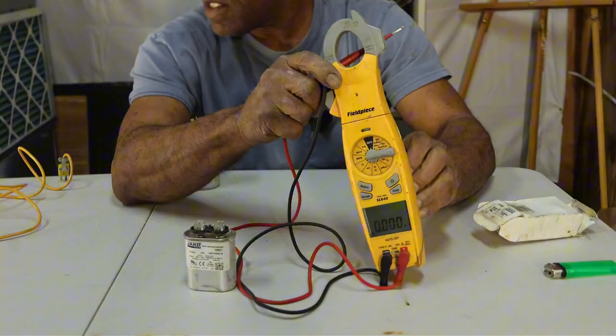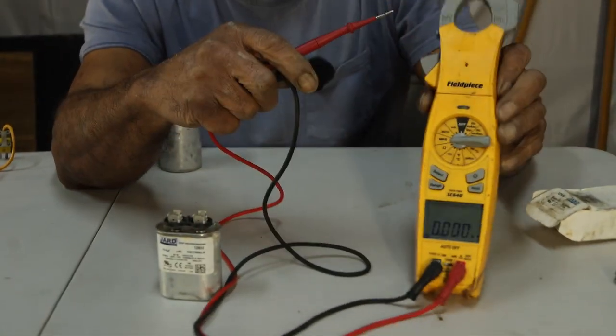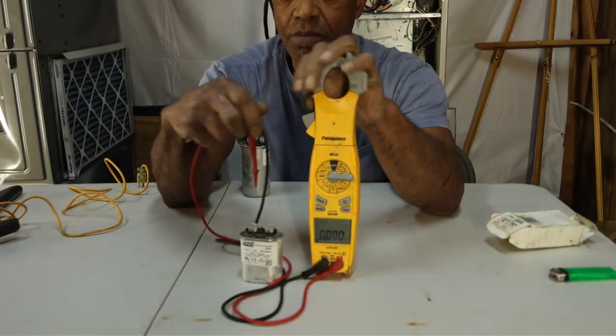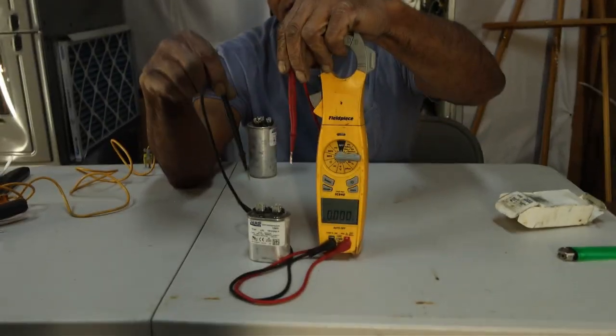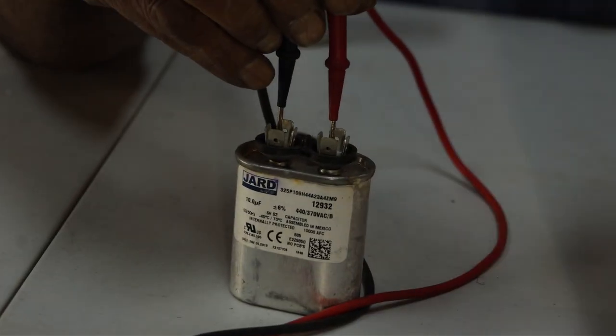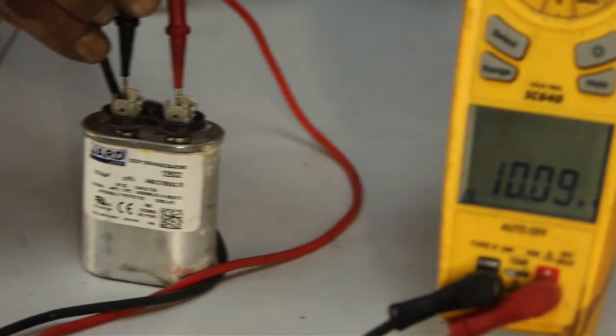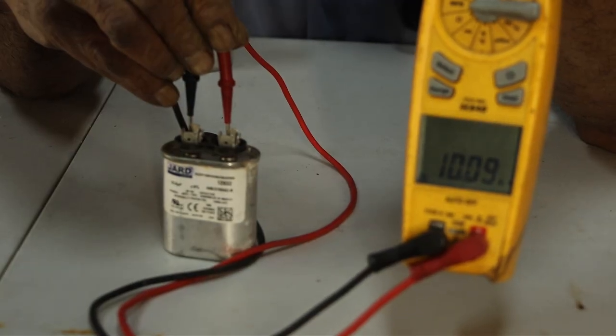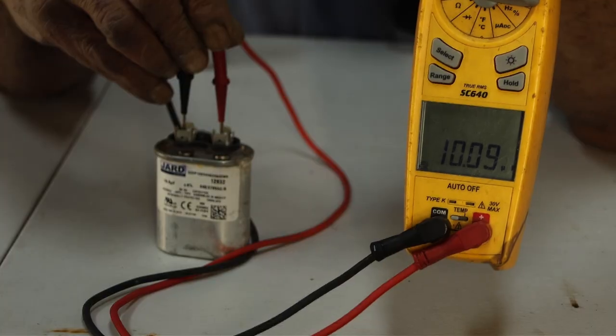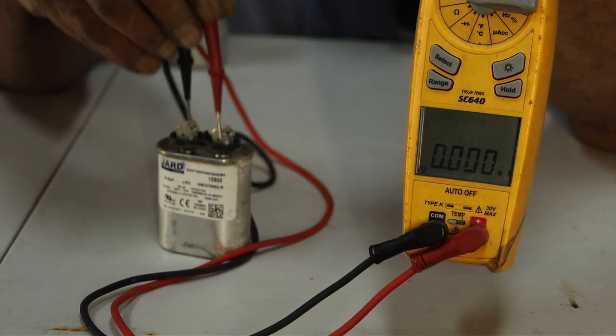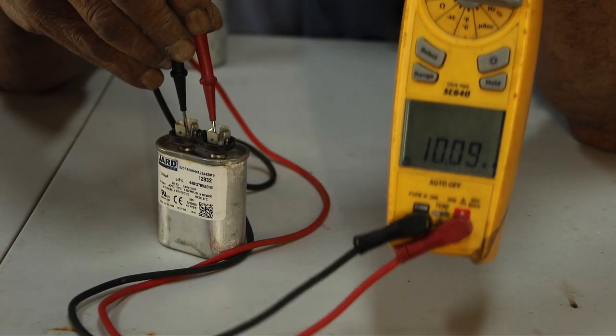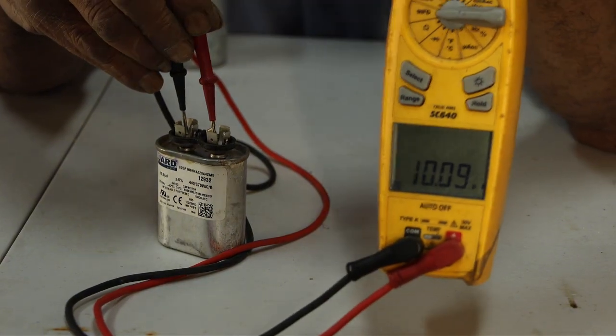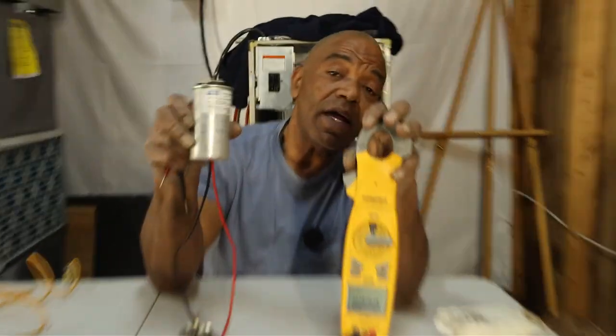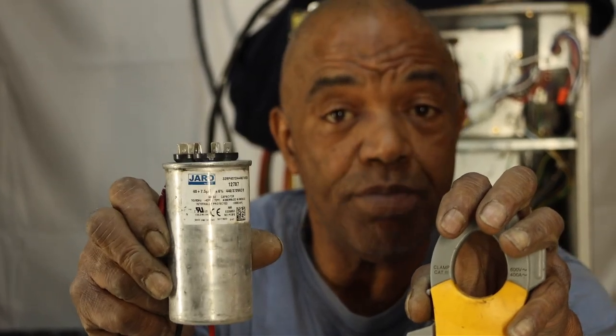But once I set my amp probe, and this is not a metal table, so it's going to be hard to get it to set up. But once I set it at the MFD, if I touch both leads on the capacitor, you should see the number 10 on my amp probe. I'm not looking at it. Is that what we see? Number 10. That tells me this capacitor is producing the 10 UF that it needs in order to start the fan motor.